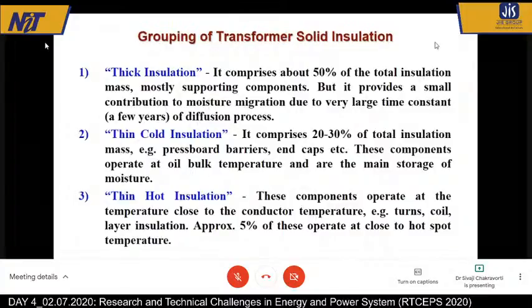30% of the mass is called thin but cold insulation. Thin, because these are mostly the end caps, the small barriers between the discs, etc. The important part is they operate at the bulk oil temperature. Now there is something here I must say. The transformers are quite big, so there is something called bulk oil temperature and something called the hotspot temperature. These hotspot temperatures are very close to the windings. Now, this thin cold insulation is generally called the main storage of moisture.